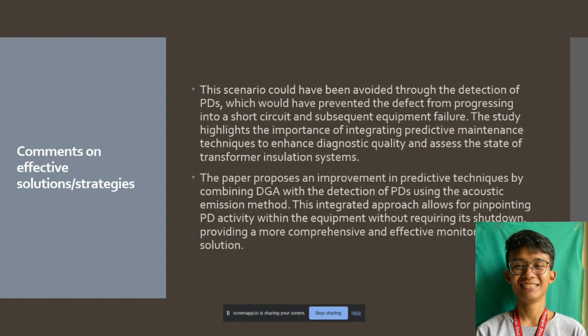For the comments on effective solutions or strategies, the scenario could have been avoided through the detection of PDs, which would have prevented the defect from progressing into a short circuit and subsequent equipment failure. So the study highlights the importance of integrating predictive maintenance techniques to enhance the diagnostic quality to assess the state of the transformer insulation systems. The paper proposed an improvement in the predictive techniques by combining DGA with the detection of PDs using the acoustic emissions method. This integrated approach allows for pinpointing PD activity within the equipment without requiring its shutdown, providing a more comprehensive and effective monitoring solution.